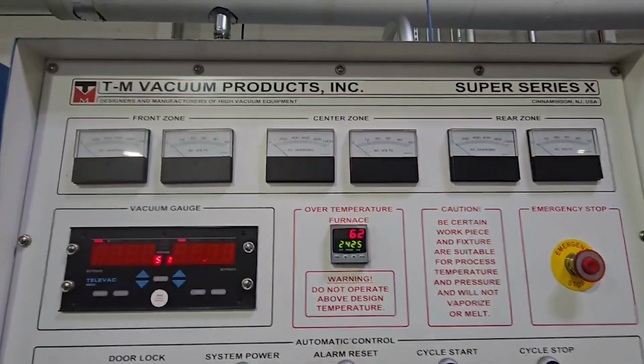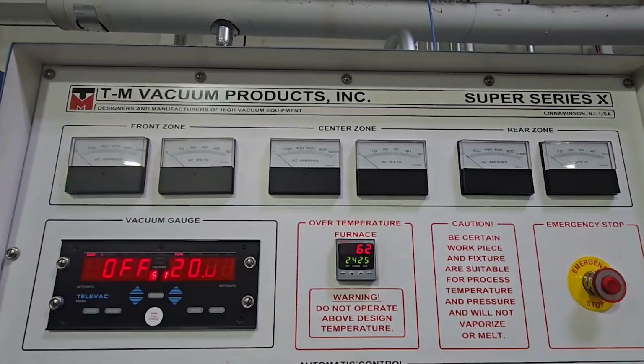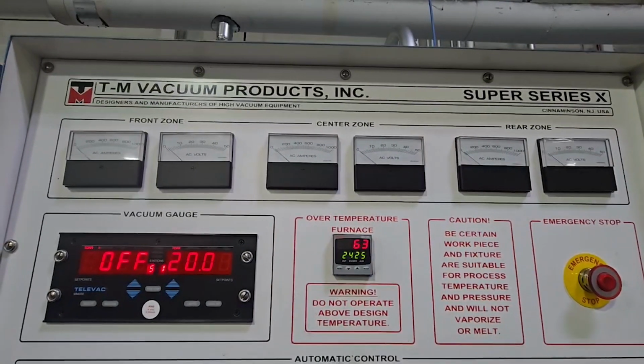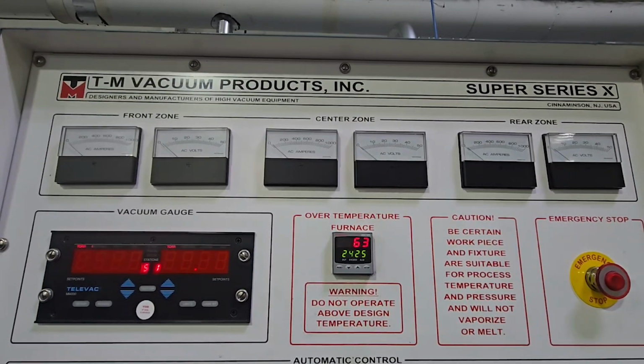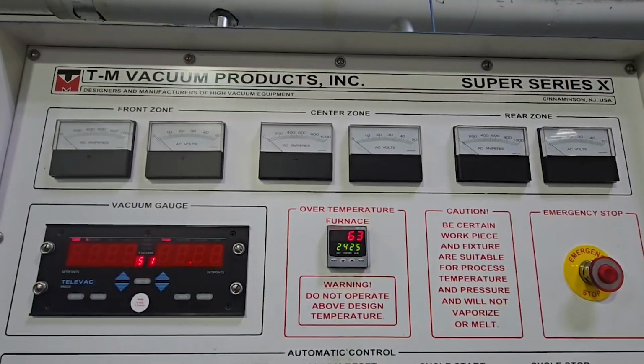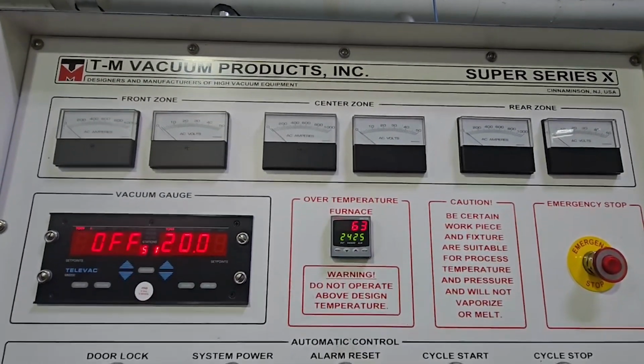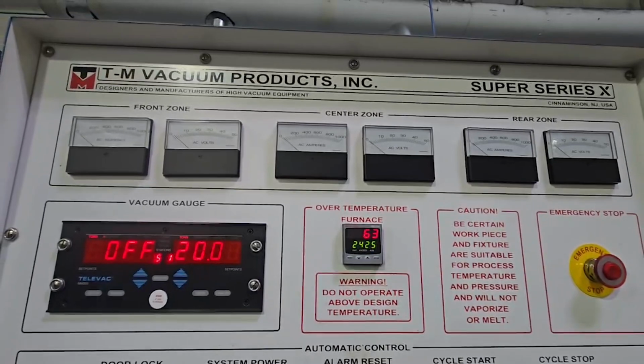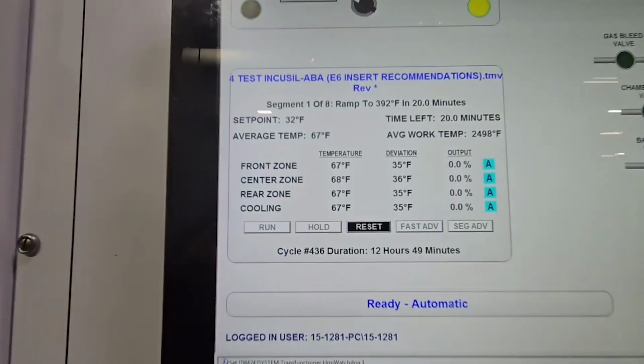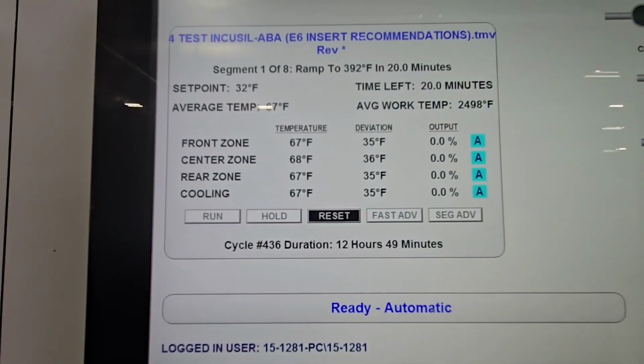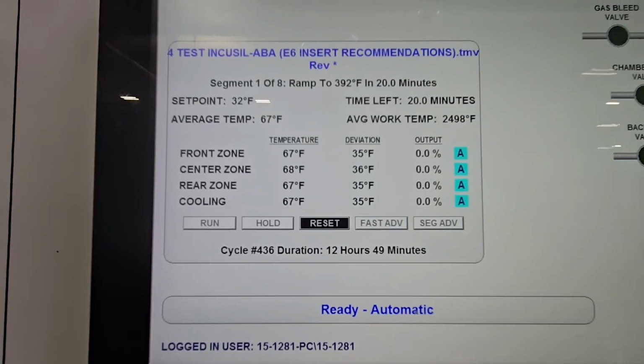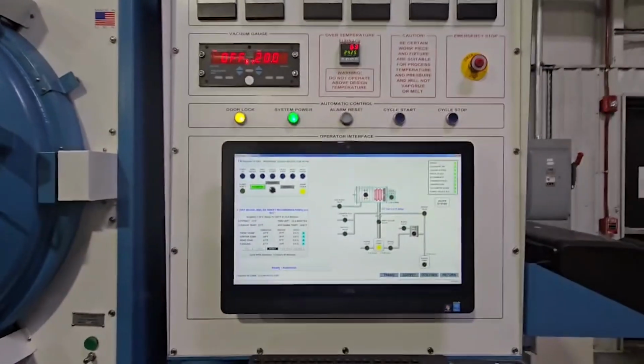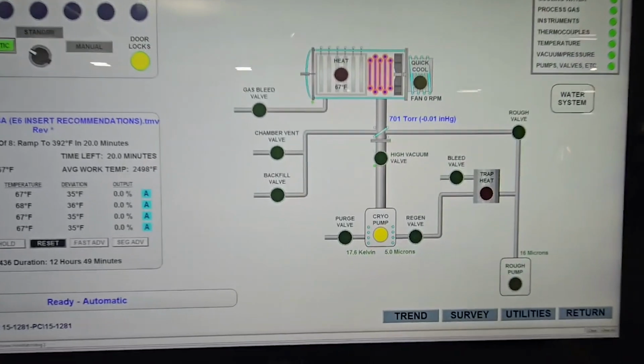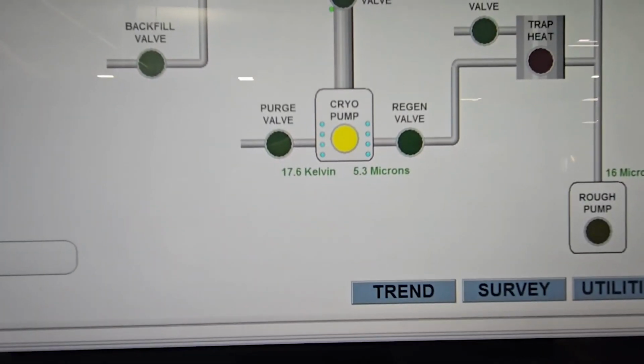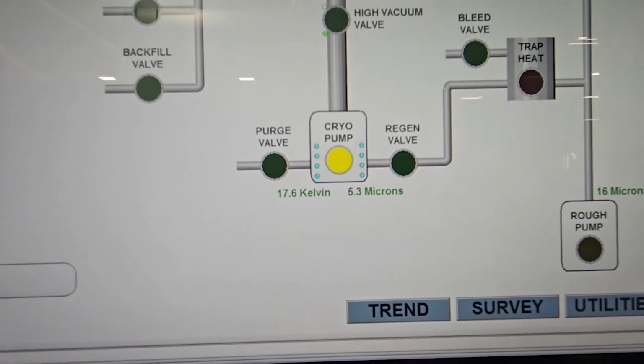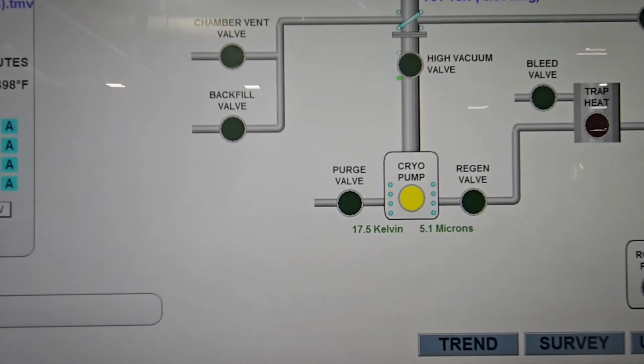The chamber has 3 internal thermocouples that read the temperature in the chamber. You have a rear zone, center zone, and front zone. That way it controls very consistent heating within the chamber. You have the regular readouts, but you also have your zone readouts that are on the display as well. Right now the cryo pump is running. It has the temperature down to 17.6 Kelvin.